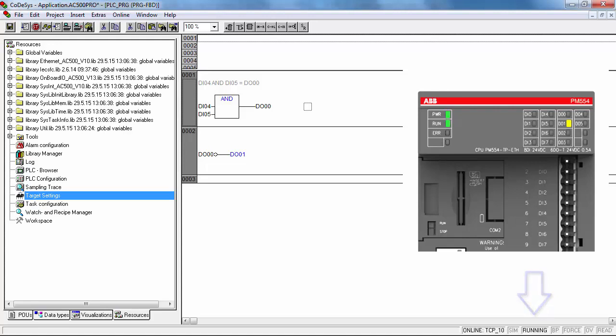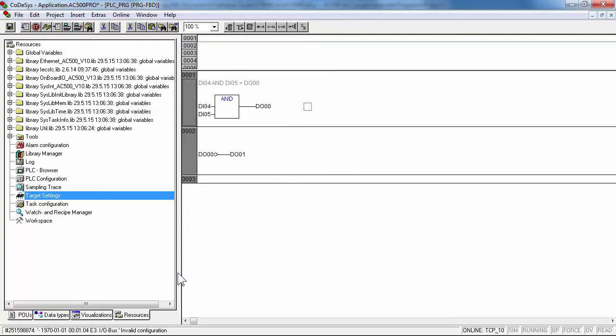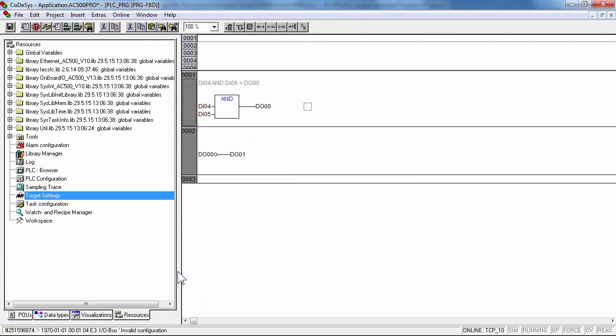So verify on CPU that the run stop switch is in run position, and that run LED in the front face is displayed in green. Save and store your project in EEPROM of CPU, using the option create boot project in online menu.